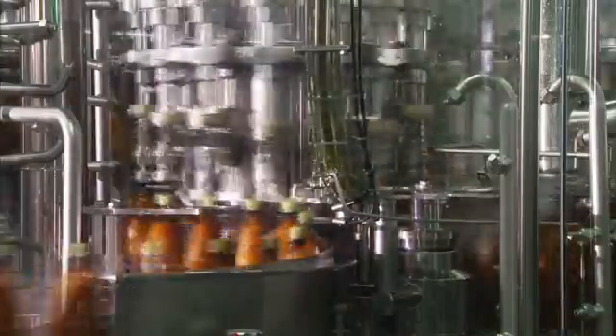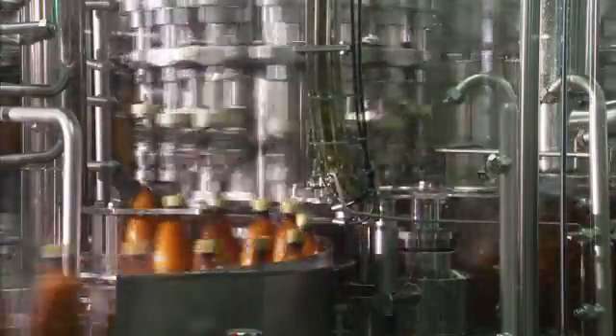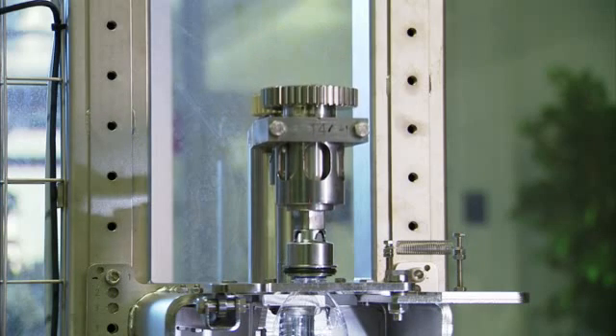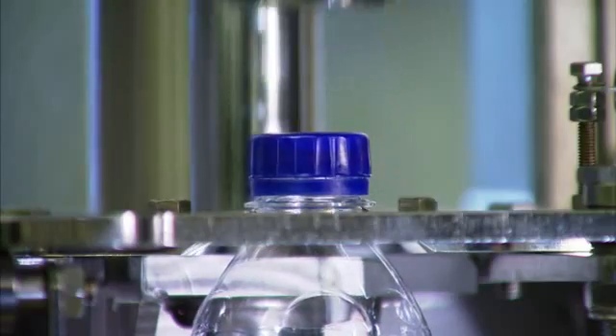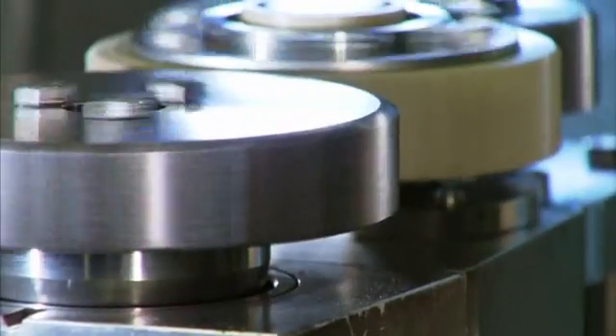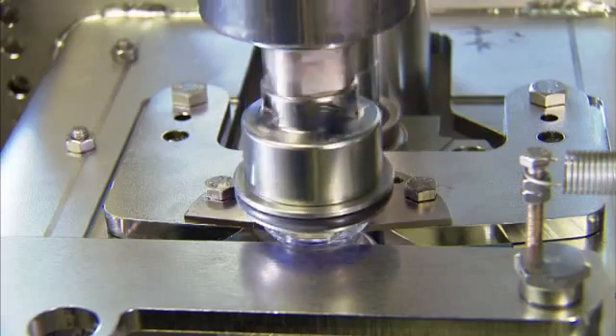In the case of the handy screw tops, the engineers of the beverage machines had to solve a particular tricky challenge. For the conventional bottling process we use mechanical drives and grease-packed bearings — with aseptic bottling this doesn't work. Our solutions are servomotors and ceramic bearings which need no greasing at all. Only in the test station can we observe, almost in slow motion, how this principle works. In reality, the bottling plant is equipped with up to a hundred such units and everything happens within seconds.